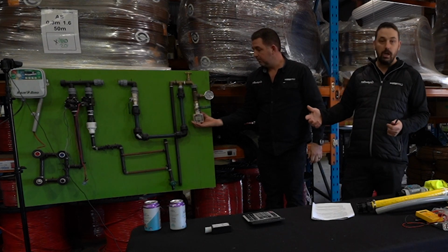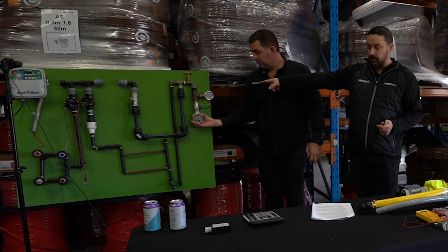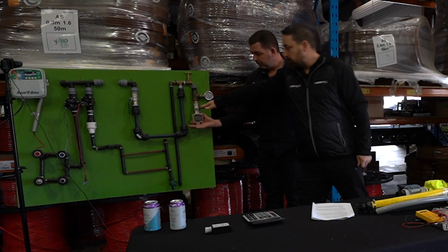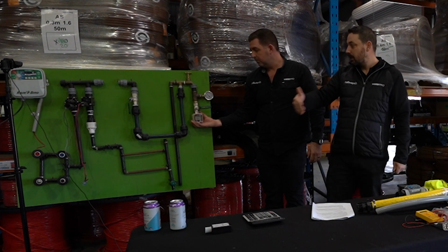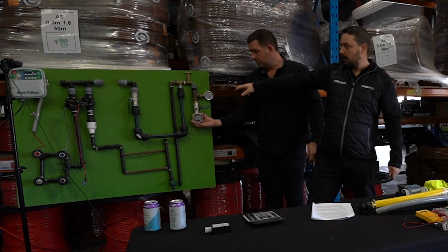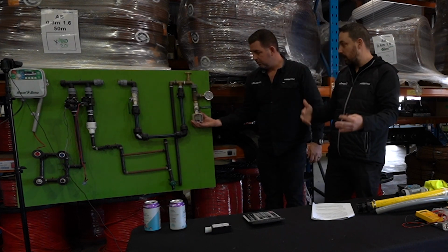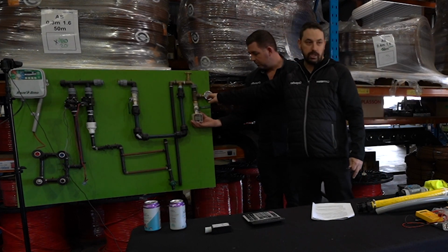Or if you're at a tap, we can actually put the pressure gauge onto our tap. Ball valve would be off because we don't want water obviously to be moving at this point. And we would turn our tap on up here, or open a ball valve or what have you, and then we would watch that pressure gauge go up.